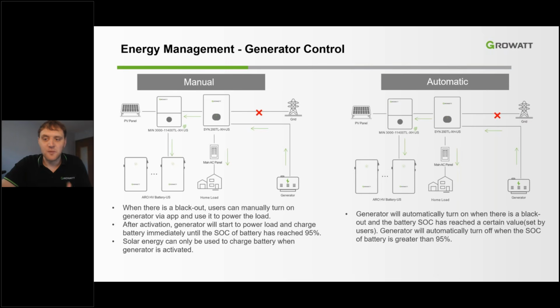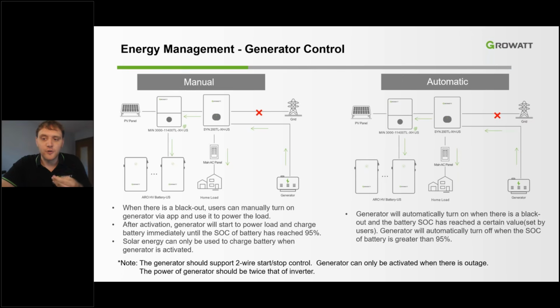The user can set the minimum state of charge that should be held by the battery before the generator turns on, allowing customers to consistently maintain the backup reserves of the battery. It is important to note that the generator will only turn on in the case of an outage, so there is no worry about the generator initiating during on-grid operations.